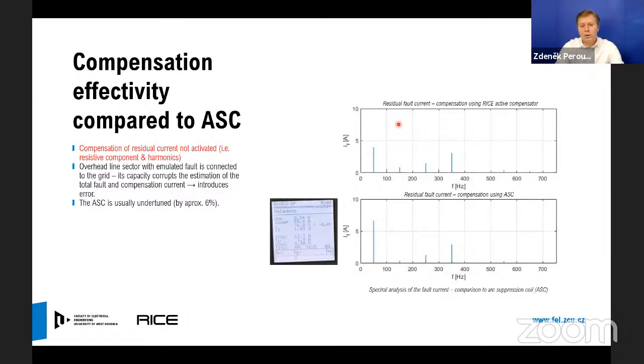We also evaluated the effectiveness of our device in comparison to an arc suppression coil. Nevertheless, we stressed our device with very strict conditions. We turned off the compensation of the residual current. It means that we turned off the compensation of the active component of the fault current as well as higher harmonics, because the arc suppression coil is unable to do it.